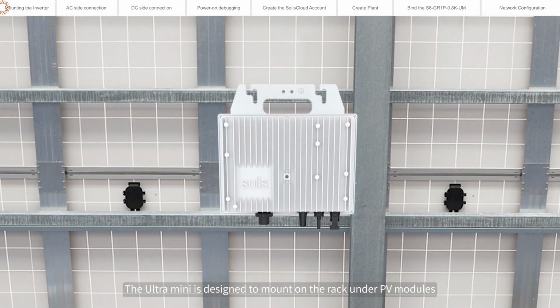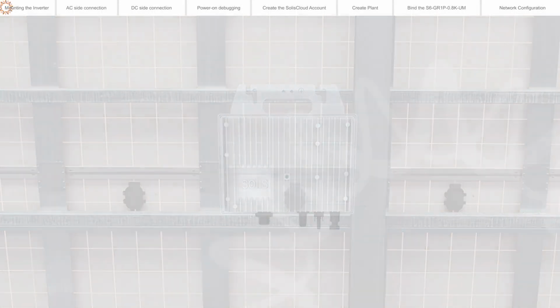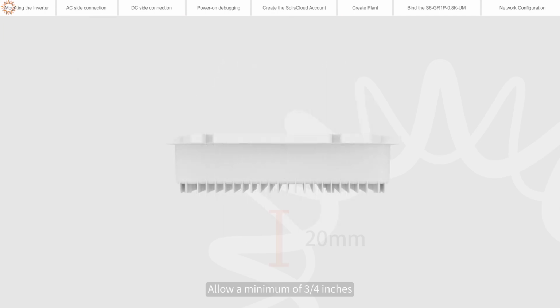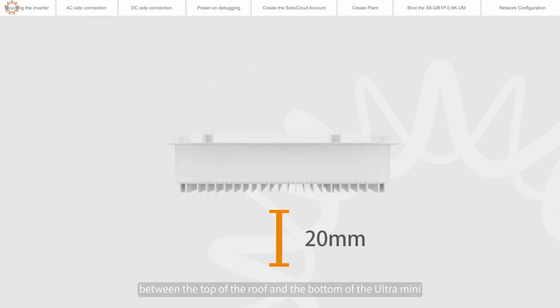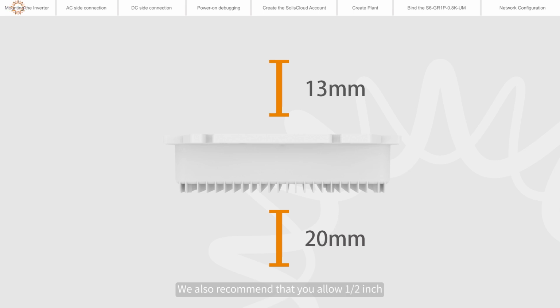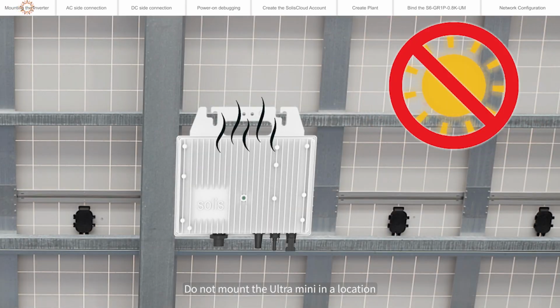Mounting the inverter. The Ultra Mini is designed to mount on the rack under PV modules. Allow a minimum of 3/4 inches between the top of the roof and the bottom of the Ultra Mini. We also recommend that you allow 1/2 inch between the back of the PV module and the top of the Ultra Mini. Do not mount the Ultra Mini in a location that allows exposure to direct sunlight.